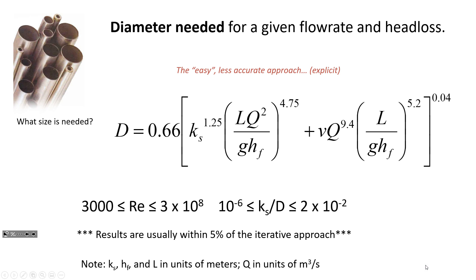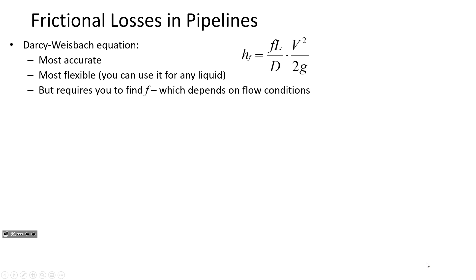The Darcy-Weisbach equation, which we've been mostly focusing on, is the most accurate and most flexible of the empirical resistance equations — you can use it for any fluid, any range of conditions, any pipe diameter. The tricky part is determining f; you can use the Moody diagram, the Jain equation, or the Colebrook equation, but it's non-trivial because f changes depending on flow conditions. The other two methods we'll look at today are easier but less accurate because their friction factor doesn't adjust with flow conditions — it's fixed.